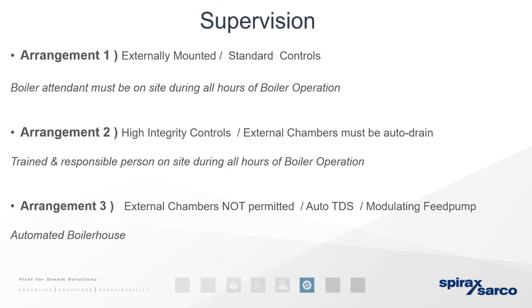Arrangement 2 is with the high integrity controls and external chambers must be auto drain. So a trained or responsible person has to be on site all hours of operation. Arrangement 3, which is external chambers not permitted, so you can't have them, they have to be internal. Auto TDS, modulating feed pump controls and an automated boiler house. So effectively nobody would need to be present. I would say arrangement 3 is quite rare in Africa.